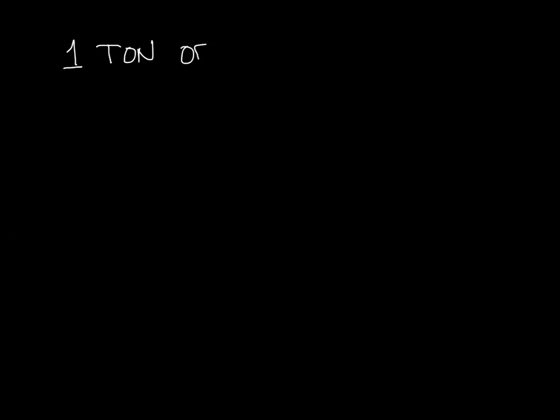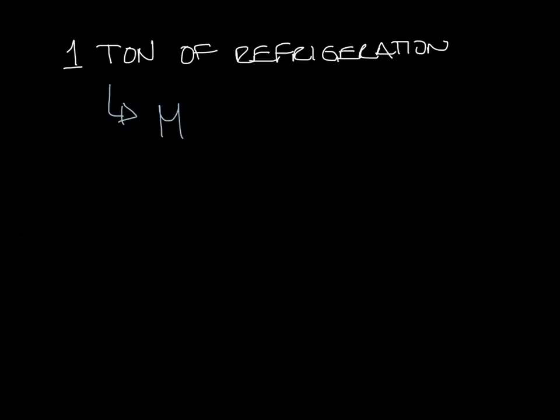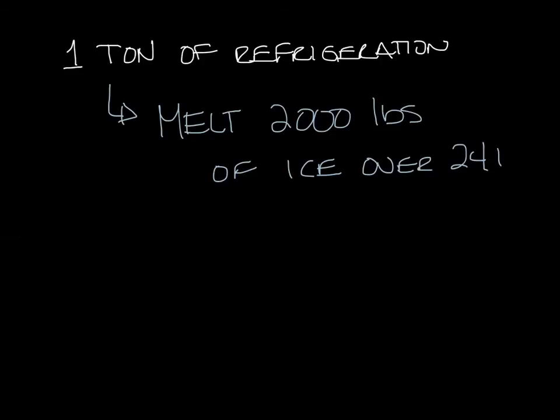Now let's talk about the ton. What is one ton of refrigeration? You hear this used all the time. One pound of water changing temperature by one degree is a pretty small amount of energy when compared to how much you need to cool an office or your home. So you hear about tons of refrigeration, like a five ton air conditioner. A ton of cooling is what would be required to melt 2,000 pounds — or a ton — of ice over a 24 hour period.